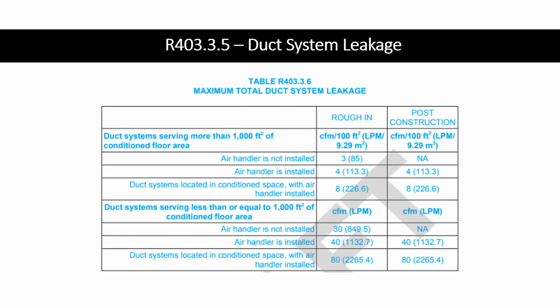So it's kind of using the same methodology, as you can tell. 3 CFM per 100 square feet, 4 CFM per 100 square feet, or 8 CFM per 100 square feet, or it's a flat 30, 40, and 80. So it's kind of using that, but you don't have enough in the calculation to get there. So I think that allowance is great to have in there. There were some above code programs like Energy Star and I think NGBS and possibly LEED follows Energy Star.